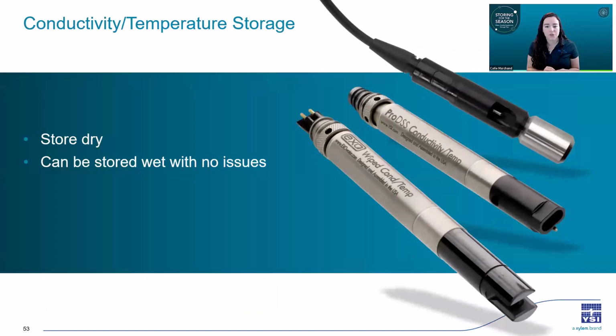CT sensors are stored dry, but they can also be stored wet with no issues and without causing problems to the sensor. So if you remove all your sensors from your instrument, just store it dry. But if, for example, you have an instrument with only CT and pH, like the Pro 1030, you can go ahead and store both sensors in pH storage solution, and it will be absolutely fine for the CT sensor.